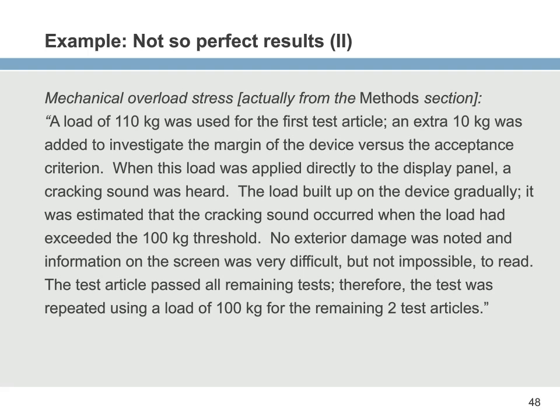And Justin, do you have some comments? When we talked about this beforehand, you had some thoughts on this kind of testing. Yeah, I think that's a good example of getting bad results, or at least results that failed your acceptance criteria, and you just need to write about them and explain it instead of trying to remove that test article from the test report and replace it. I think when you hide things, move things away, or call them outliers is where trouble happens, where warning letters happen, and where your submission won't get through the process. So that's a pretty good example where you had a bad result - you were trying to add a safety factor, it didn't work out, but you just wrote about it. You were upfront about it and moved on.